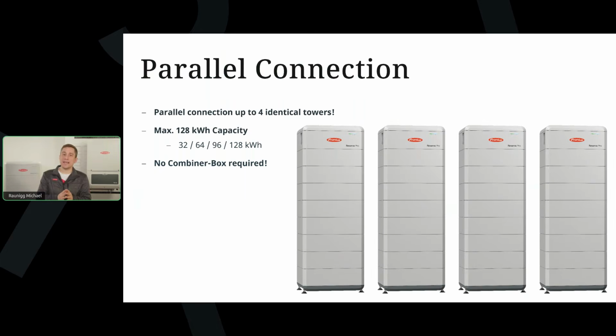A very nice feature of the Reserva Pro is that we don't need any DC combiner boxes between the battery systems. Whenever you want to install a second, third, or fourth tower, all you need to do is the DC cabling from one battery to the other, without any DC combiner boxes or DC strings in between. This makes for a very smooth installation system. All you need to do is confect your cables, make them ready, and then just click and connect them to each other.